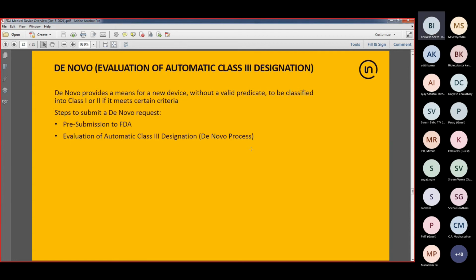Now, once a De Novo is cleared, automatically a classification category is created. So think of this in a scenario where company A submits a De Novo. So they didn't have a classification for the product type. FDA made them do a De Novo, and now that product is in the market. The De Novo has been approved. Company B later decides to market a similar device, but now they can use company A's device as a predicate device. So now company B doesn't need to do a De Novo. They can simply do a 510K because now a classification exists and now at least one predicate device exists in the US market. So that's how the De Novo approach works.